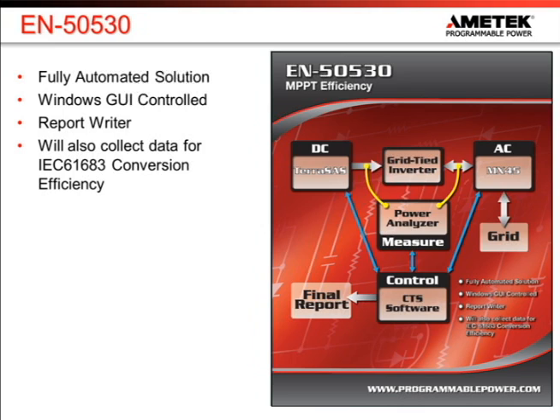Building yet further on the all-around inverter test concept, this solution utilises our TerraSAS PV Simulator, MX45 Grid Simulator, and Compliance Test System to provide a fully automated test solution for EN50530. This is Windows GUI controlled, features a report writer, and has the ability to collect the data needed for IEC 61683 conversion efficiency.